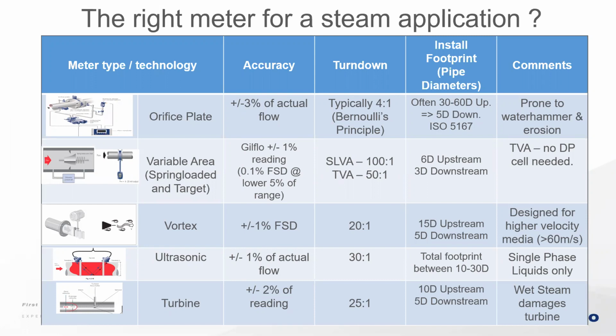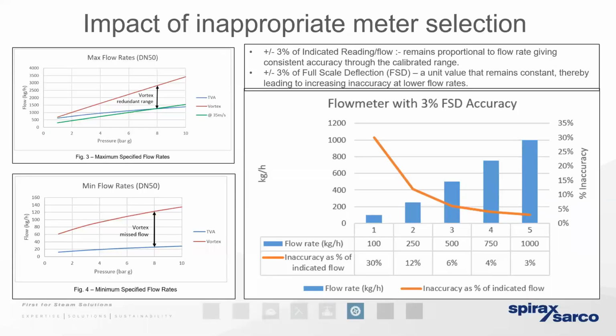But I think the key things to bear in mind are phrases that we use, such as turn down. That's essentially the difference between the highest and the lowest loads that the meter will need to read. We've got the accuracy, the ability of the meter to take a true and correct value. And we've got the repeatability, the ability of the meter to read the same value twice. That could be an incorrect or inaccurate reading, but it's the ability to take the same reading on more than one occasion. With regards to accuracy, it's important to understand that different manufacturers will quote accuracy in different ways, and this can be really misleading.